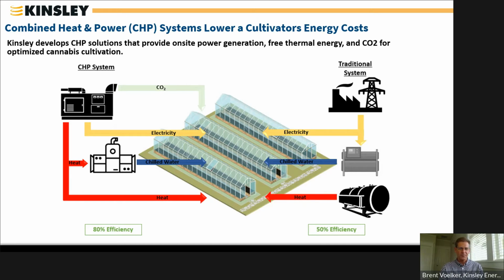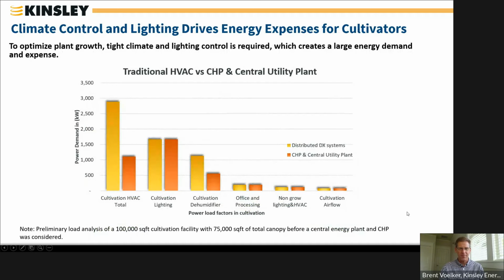So if you go to the next slide, this shows an example of a same facility, about 75,000 square feet of canopy. It started off as a 6 megawatt load. And after adding central utility, high efficiency chillers, energy recovery, air handlers, and CHP, it becomes more like a 3,200 to 3,500 kilowatt facility. So reducing your total power demand almost in half. At that point, you may have a cooperative utility who can provide that much power and still want to interconnect your CHP system so that you've got a redundant system where the CHP is backed up by the utility.